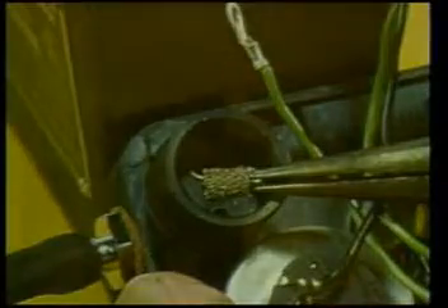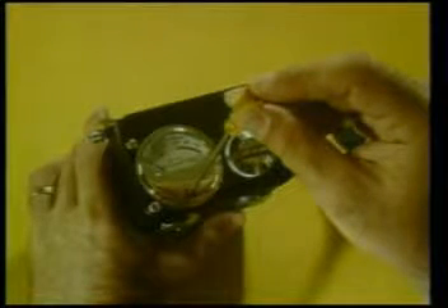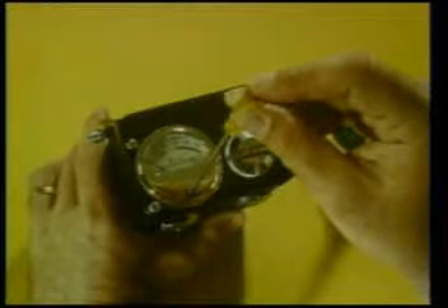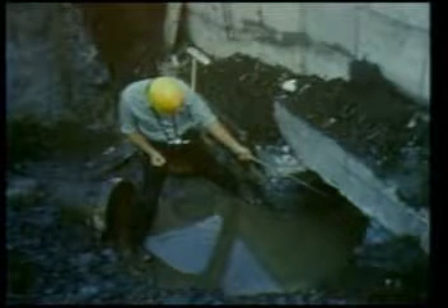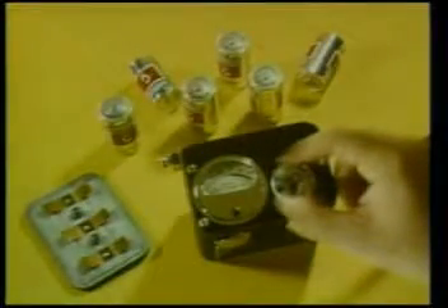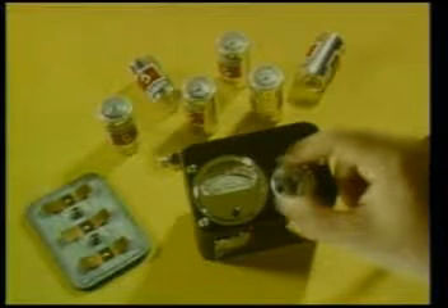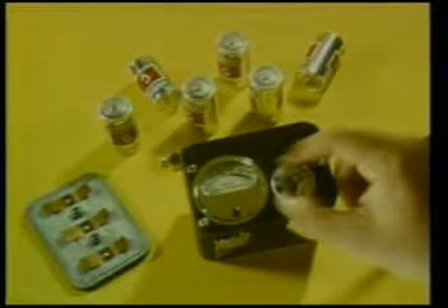Other adjustments to the explosimeter indicator include the mechanical zero setting. If the meter needle does not rest on zero with the instrument turned off, it can be reset by turning the screw on the meter face. If the instrument hasn't been used for a while, or if samples have been taken in severely corrosive atmospheres, the contacts of the rheostat may become tarnished. The instrument's response will be erratic. To correct this, remove the batteries and turn the operating controls back and forth a number of times to clean the contact points.